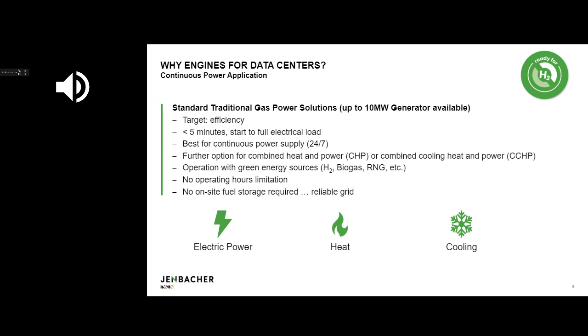There's also an option called trigeneration, or combined cooling, heat and power. Here you generate power as baseline, recover the heat, and with this heat you use a chiller to generate cooling. So you have continuous power for the data center, heat that you may require for your installation systems, and also cooling to use in chillers, for example. So you have a much more complete solution, and here we're talking about efficiencies of about 90%.